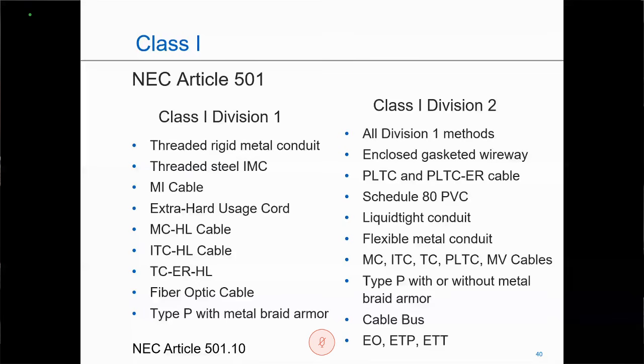And then in 1999, they added instrument tray cable with the HL designation for Division 1. And then in 2014, the tray cable exposed run. In 2020, Type P with the metal braided armor was added as a Class 1, Division 1 wiring method.